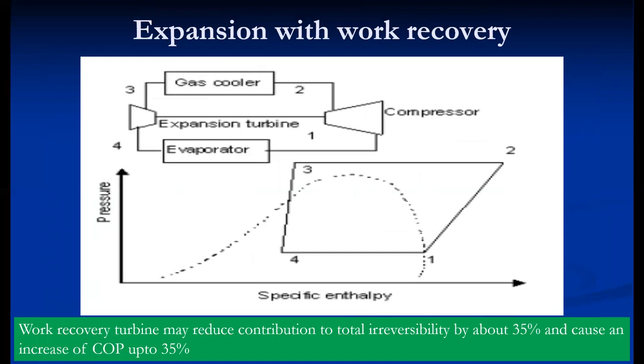The second modification: instead of an expansion valve, an expander is used — similar to the expander used in air refrigeration systems. When we use an expander, it is essentially coupled to the compressor, which should be a centrifugal or axial flow compressor. So the compressor and turbine are coupled to each other. Starting from point one, one to two is the normal compression process, two to three is gas cooling, and three to four is isentropic expansion in the expander device. The expander generates some power that is given to the compressor, so additional work is recovered. That is why it is called expansion with work recovery.